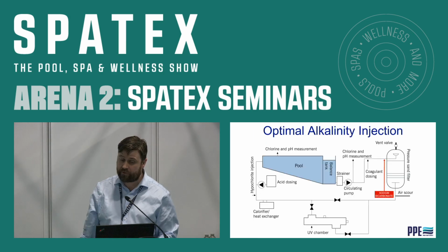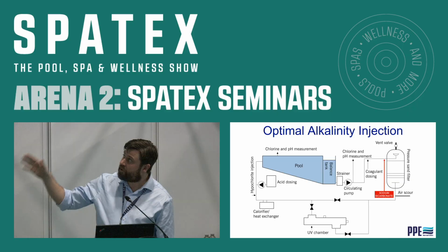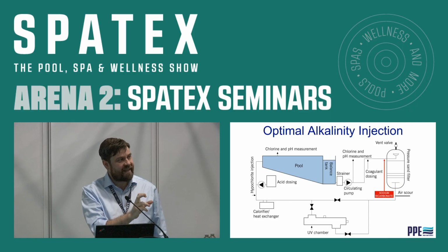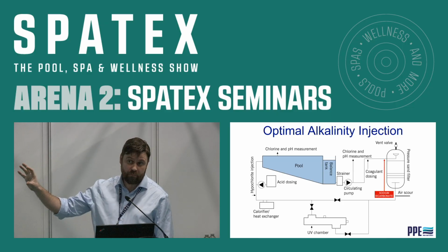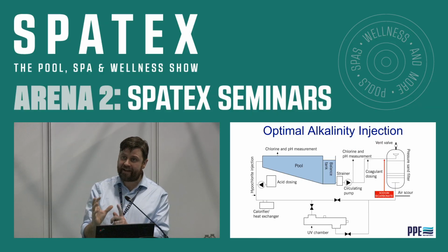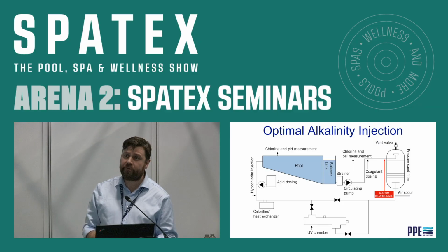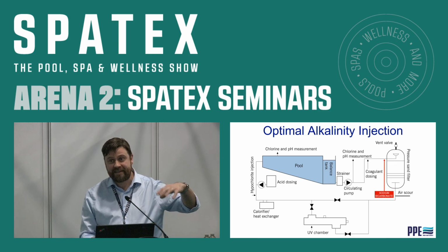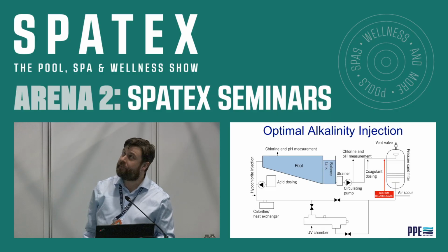And your plant system would look something like this. Okay. So if we put the sodium bicarbonate in just pre-filter, what we're guaranteeing is where the coagulant's been injected, we're actually going to get that localized higher levels of total alkalinity, ensuring that actually within the filter itself, we're going to have an acceptable flock bed actually being manufactured because it's got the ideal conditions. The other benefit is with steel filter vessels, we're actually pushing up the Langelier index or water balance index within the filters. And we have that other bonus of it's got to go all the way around the system before it gets picked up again in the measuring cell.